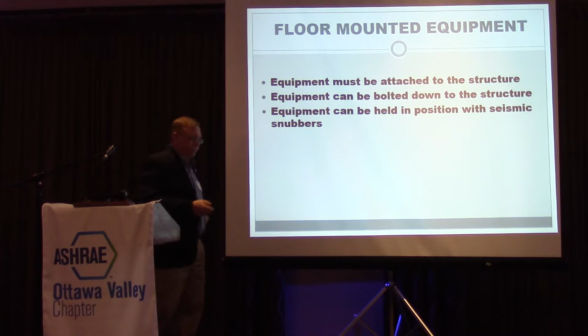Let's start with just floor-mounted equipment that's hard bolted down—that's the easiest. So what we found at Northridge was a lot of bolts that were just sheared off. And they weren't big pieces of equipment that should have failed given the earthquake—it turned out they were small pieces of equipment, but what happened was they went back and forth. Earthquakes could have hundreds of cycles back and forth.